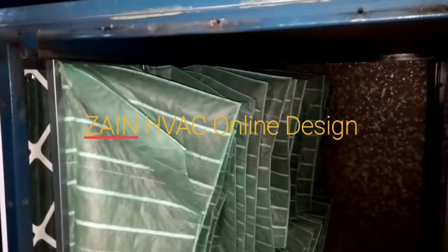So this is a digital reader here, and you can see the supply side is being read through the pipe there, or the tube, and then this tube is going around to the other side of the filters. It's just a hollow tube really, which is going to suck that in and take the pressure reading across it. It's a slightly different type, basically taking the pressure reading across the filters, and it will send an alert to the BMS that the filters are ready to be changed because the pressure drop has increased too much, indicating that it is dirty.